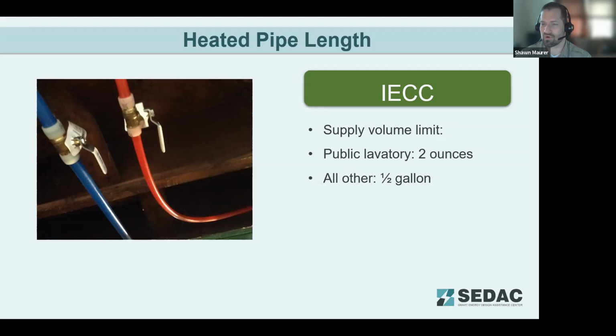So as we can see, this requirement either requires point of use heaters or a temperature maintenance or circulating system in most commercial buildings. It's very rare that you're going to be able to have a water system at a central location distributing out to remote rooms that's going to be under 2 ounces or a ½ gallon.